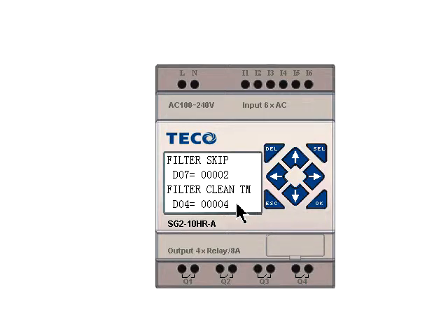And then this is how long the filter clean time is. It's set at 4 seconds. Anywhere from 4 to 8 seconds, depending upon the application, would be appropriate. Coming down, this is your on-off setting for the filter. So it's on for 4/10 of 1 second, and it's off for 6/10 of a second. That's how it goes out of the factory. It's not normally necessary to change that, but if you want to play around with it, this is where you would do it.